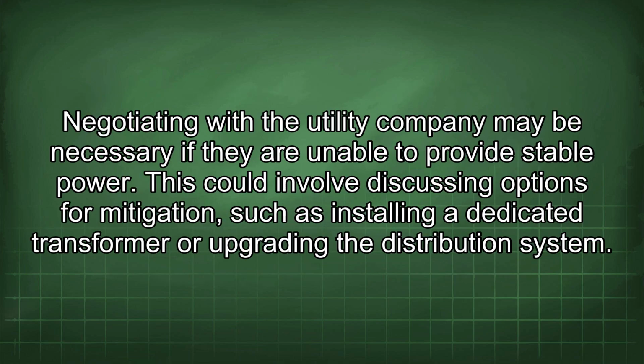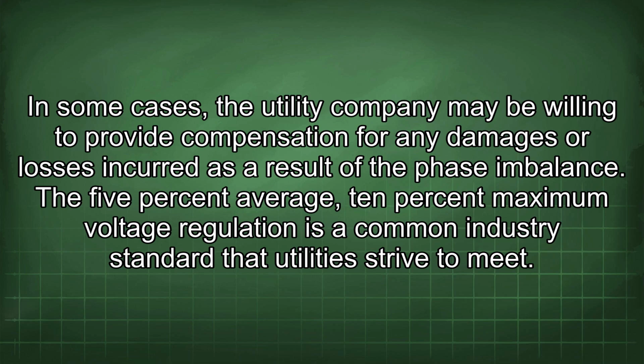Negotiating with the utility company may be necessary if they are unable to provide stable power. This could involve discussing options for mitigation, such as installing a dedicated transformer or upgrading the distribution system. In some cases, the utility company may be willing to provide compensation for any damages or losses incurred as a result of the phase imbalance.